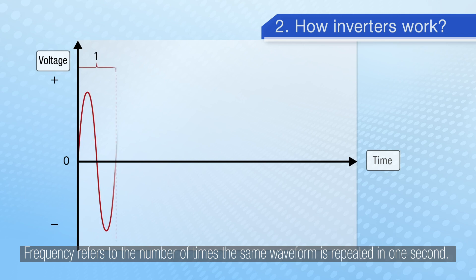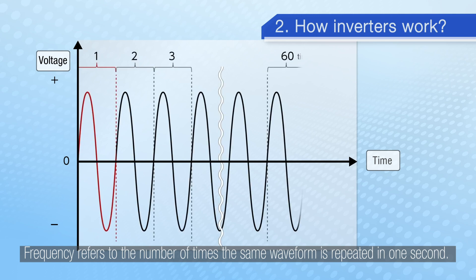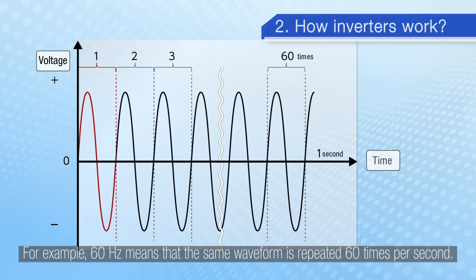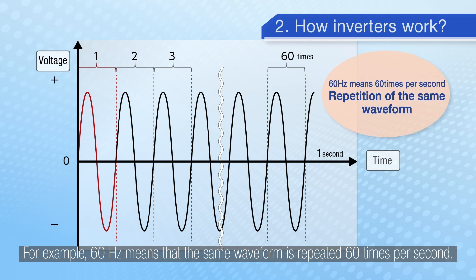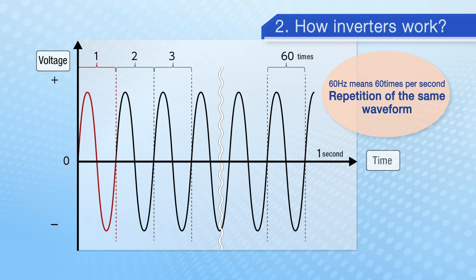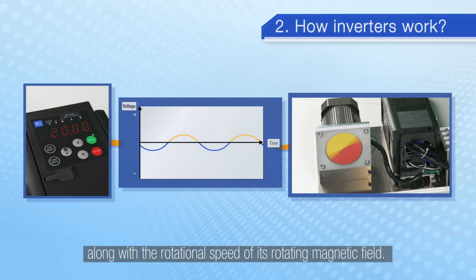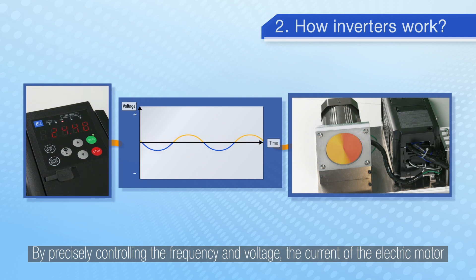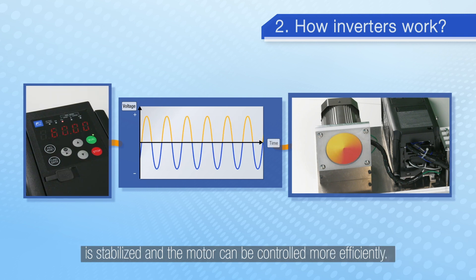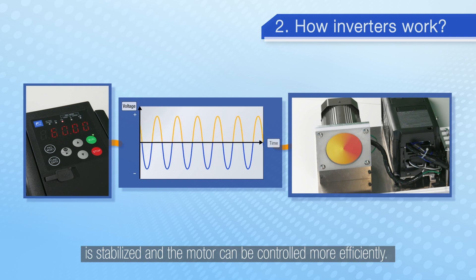Frequency refers to the number of times the same waveform is repeated in one second. For example, 60 Hertz means that the same waveform is repeated 60 times per second. As the frequency and voltage change, the motor's rotational speed changes along with the rotational speed of its rotating magnetic field. By precisely controlling the frequency and voltage, the current of the electric motor is stabilised and the motor can be controlled more efficiently.